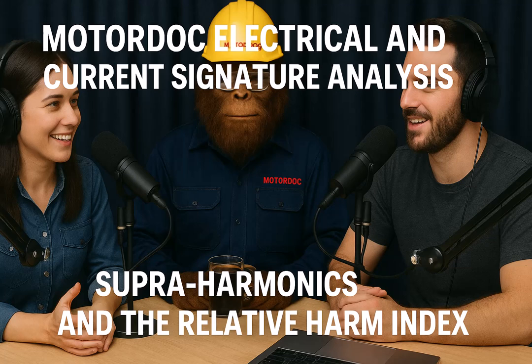Right, the dB we talked about. Exactly, and also the actual frequency of the harmonic. The core idea is that higher frequencies tend to cause damage more quickly. So the calculation involves squaring the ratio of the harmonic frequency to the fundamental frequency, which reflects the increased harm potential at higher frequencies, combined with that dB level. Okay, so frequency matters a lot. How do we interpret the RHI scale then? What do the numbers mean?